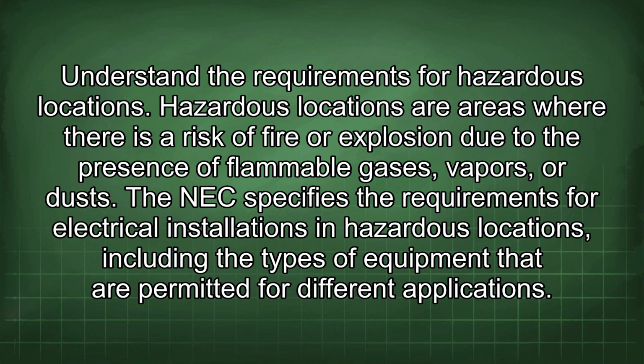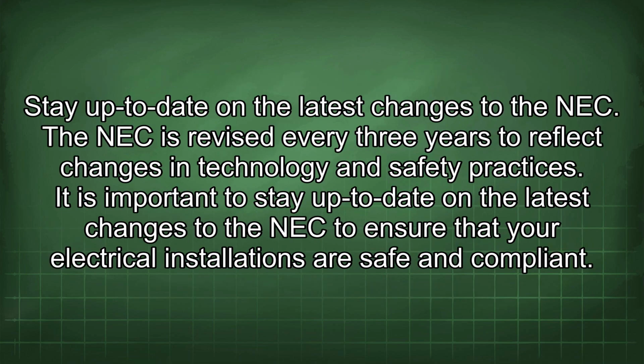Understand the requirements for hazardous locations. Hazardous locations are areas where there is a risk of fire or explosion due to the presence of flammable gases, vapors, or dusts. The NEC specifies the requirements for electrical installations in hazardous locations, including the types of equipment that are permitted for different applications. Stay up to date on the latest changes to the NEC. The NEC is revised every 3 years to reflect changes in technology and safety practices. It is important to stay up to date on the latest changes to the NEC to ensure that your electrical installations are safe and compliant.